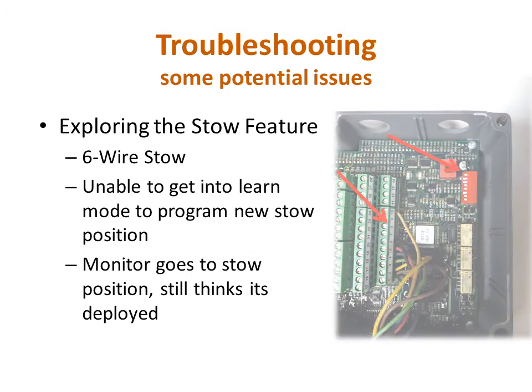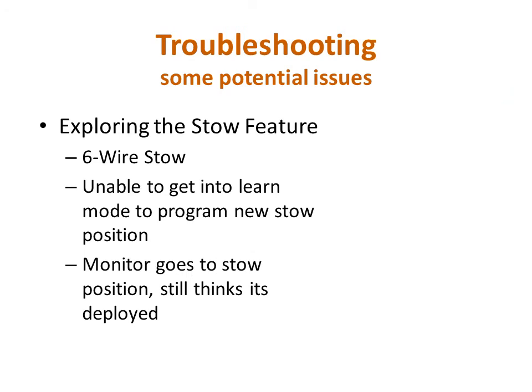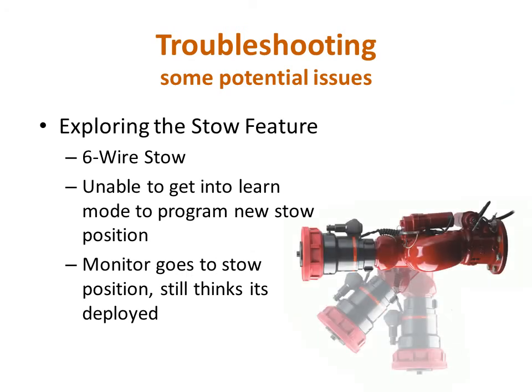This next condition is tied to specific stow positions. For instance, if the monitor is mounted under a ladder and is stowed with the nozzle tucked up against the underside of the ladder. If the monitor goes to its stow position and either generates an error or doesn't turn off the stow light, it is likely because the stow position that is programmed is too close to the hard stop or limit of travel. If this happens, simply relearn the stow position, but back off slightly from the hard stop.